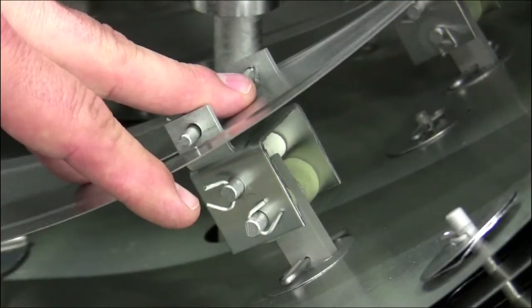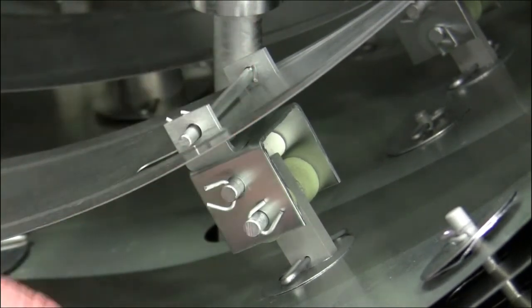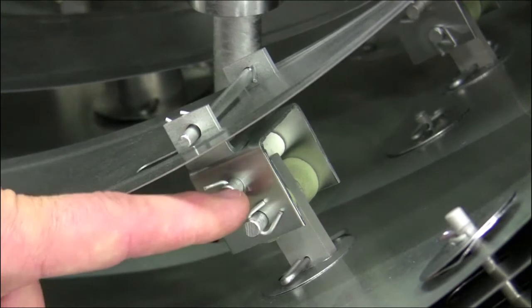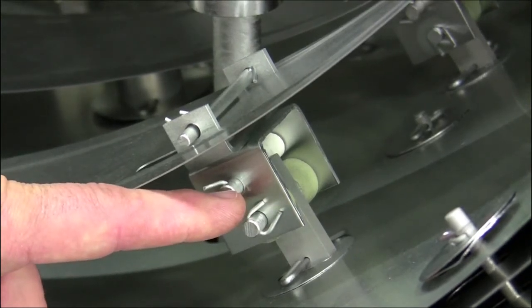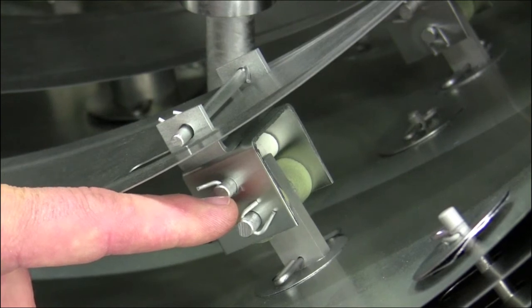When the hot zone is first installed and relatively new, the reading or resistance drop between the heating elements and ground should be nothing. As the ceramics become contaminated with process materials, it becomes necessary to keep a watchful eye on them.